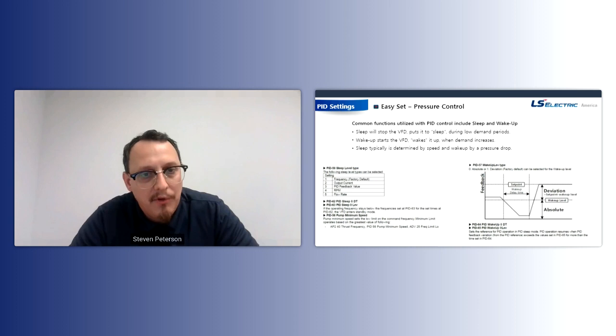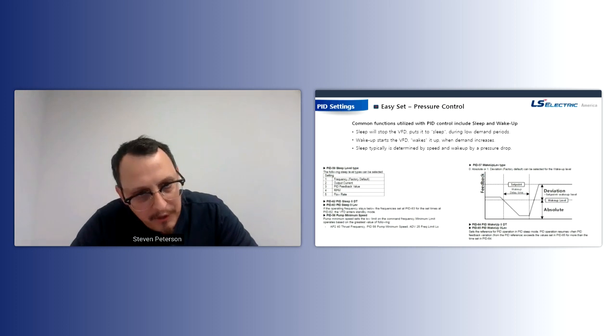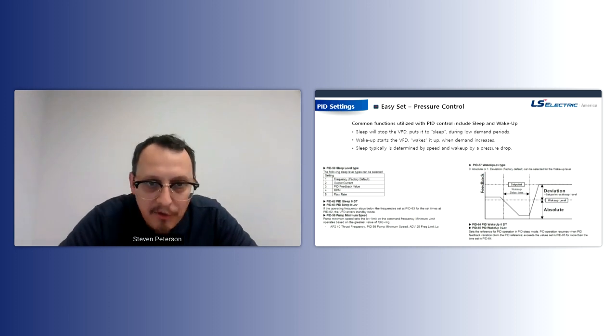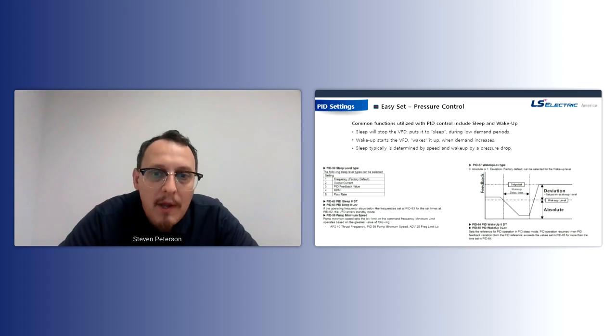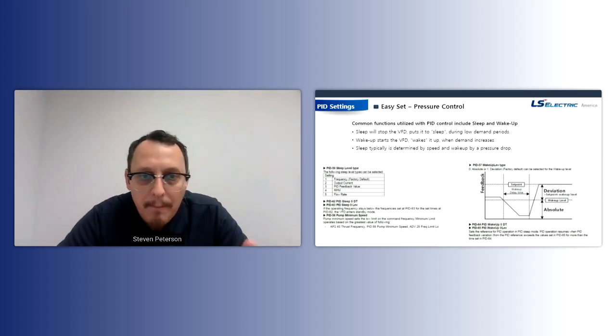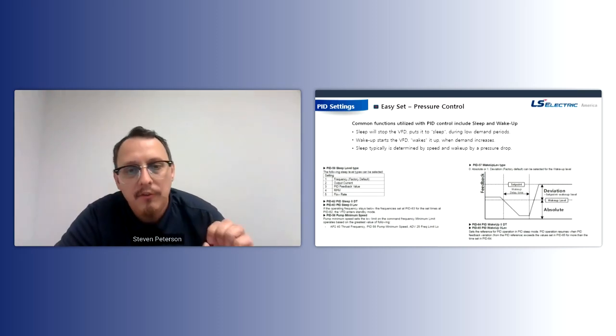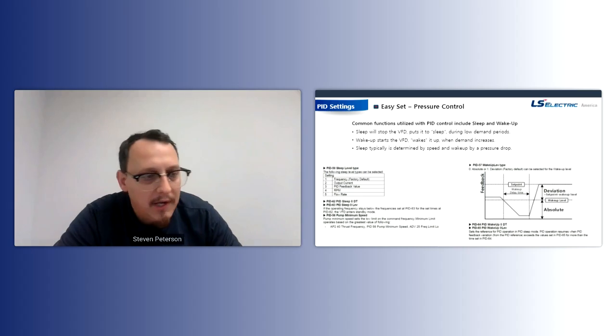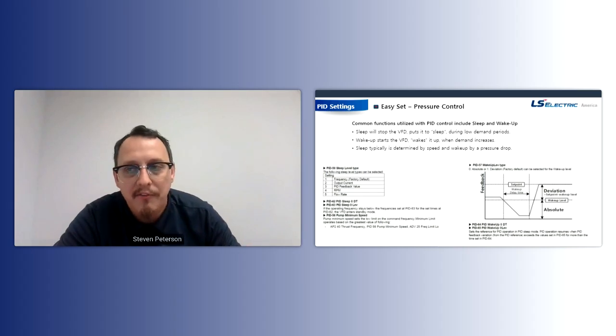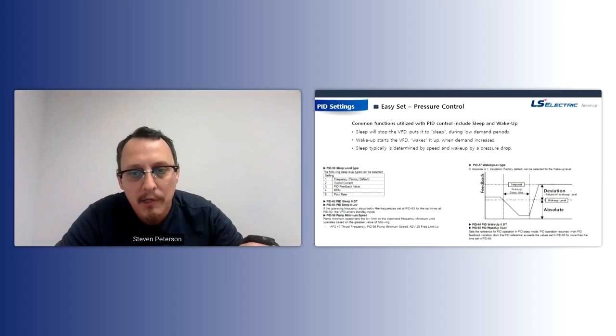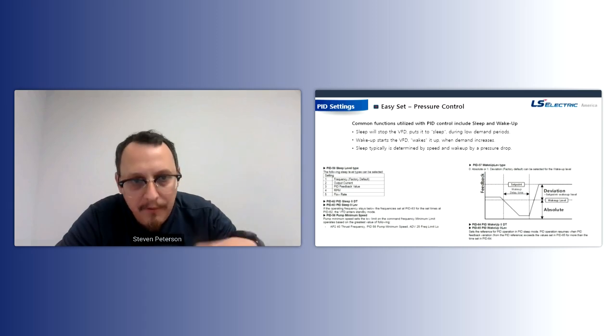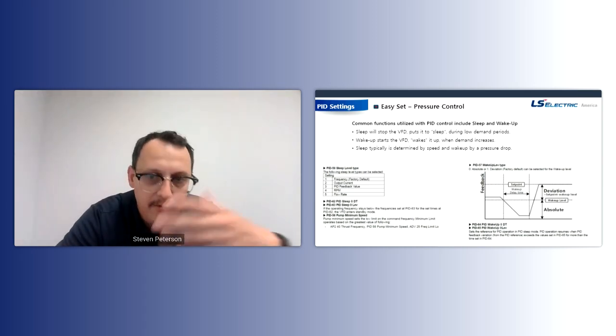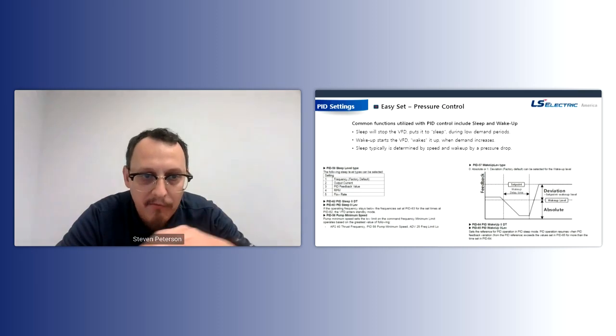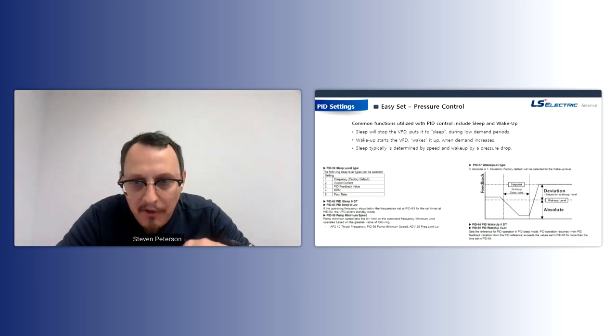Then we have the opposite of that, which is wake up. You can't go to sleep before you set your alarm. That's the best way to explain that. You need to set up a wake up alarm. And the wake up is typically a pressure drop. Okay. By default, our drive is going to use a deviation. So if you have a 60 psi set point and a 10 psi deviation, the drive is going to wake up after a 10 psi drop. So 60 drops to 50. Okay, pressure's low enough. Let's start up again. That's your wake up level. Okay. And these are customizable.